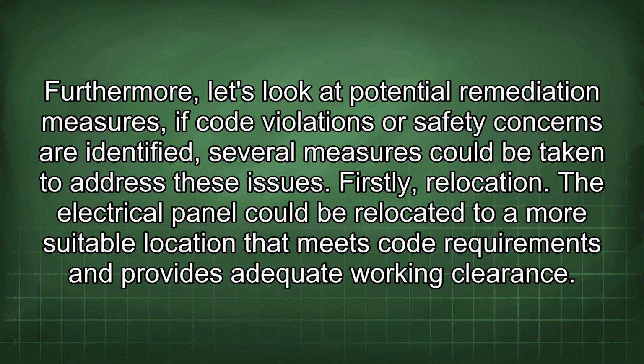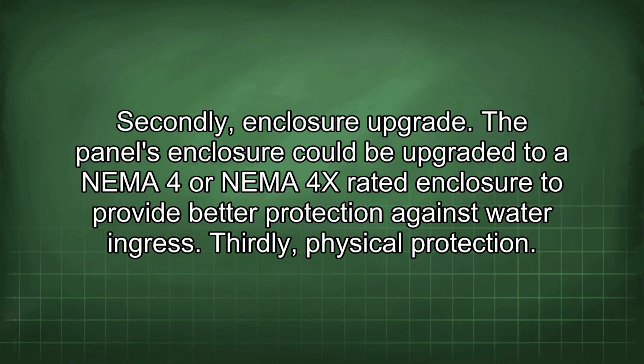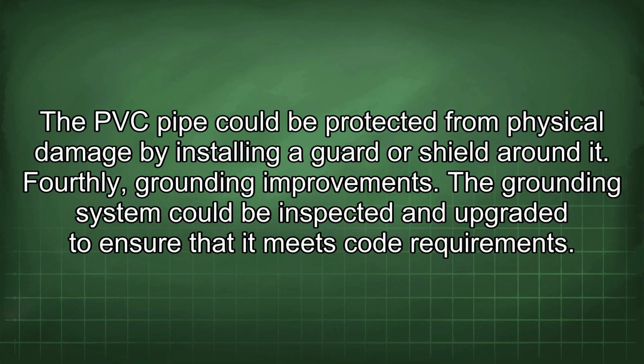Furthermore, let's look at potential remediation measures. If code violations or safety concerns are identified, several measures could be taken to address these issues. Firstly, relocation. The electrical panel could be relocated to a more suitable location that meets code requirements and provides adequate working clearance. Secondly, enclosure upgrade. The panel's enclosure could be upgraded to a NEMA 4 or NEMA 4X rated enclosure to provide better protection against water ingress. Thirdly, physical protection. The PVC pipe could be protected from physical damage by installing a guard or shield around it. Fourthly, grounding improvements. The grounding system could be inspected and upgraded to ensure that it meets code requirements.